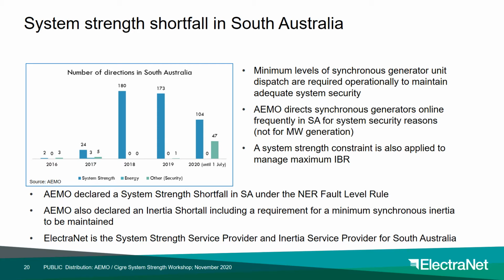With the ongoing reduction in operational dispatch of synchronous generation for South Australia, AEMO was required to commence directions of synchronous generators to ensure minimum acceptable levels could be maintained. The graph on this page shows directions for South Australian generation in the last 5 years. It can be seen that between 2017 and 2018, a substantial increase in directions were required to ensure acceptable minimum levels of synchronous generation dispatch could be maintained. It is important to note that these directions are for system strength and not to ensure supply-demand balance is achieved.